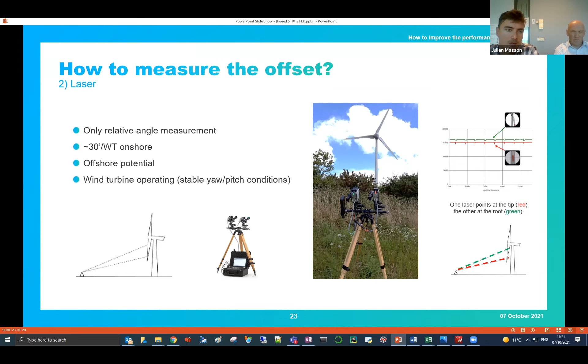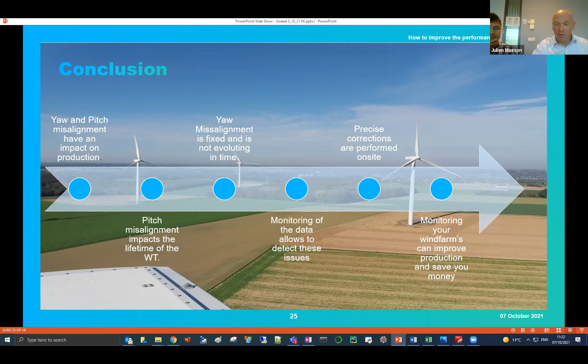Now, some conclusions. As explained, you now know that yaw and pitch misalignment have an impact on production, and especially pitch misalignment has an impact on the lifetime of the turbine. The yaw misalignment doesn't change over time, so it appears directly from the start of the lifetime of the turbine. Performing a yaw scan is, for us, a good way to identify a misalignment and to save money. So that was it from our side. We tried to respect the timing. I hope, are there any questions?